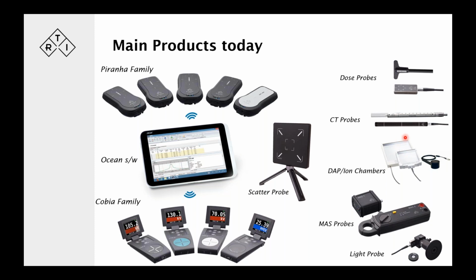Thanks to the versatility of the system packaging, we can attach also DAP chambers and other ion chambers apart from the CT ion chamber to measure, for instance, mammo dose with ion chambers, or DAP or CAP measurements made in panoramic or CBCT dental, for instance, where it's difficult to measure a decent CTDI value due to the fact that many of those gantries don't perform a symmetrical scan, have a non-circular shaped movement of the gantry. So this smaller one is suitable for that. You place that on the tube side and measure all output from the tube. So you get the DAP value that way.